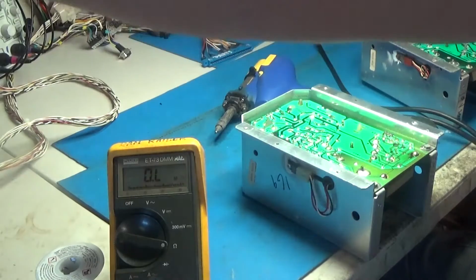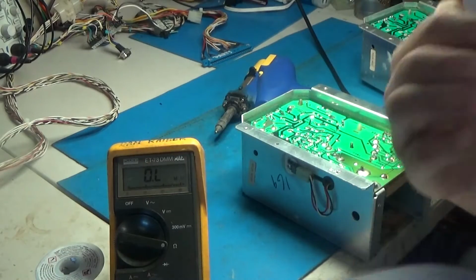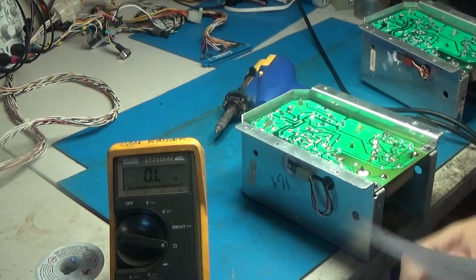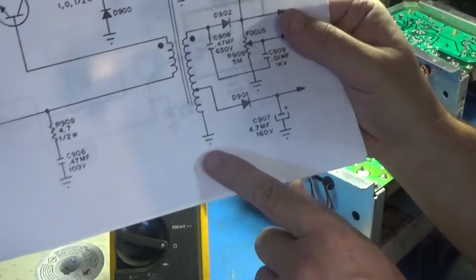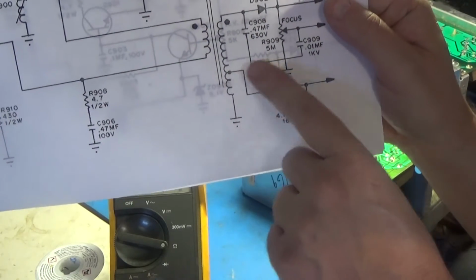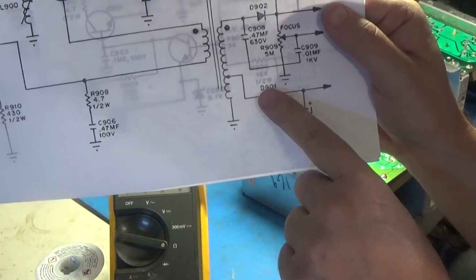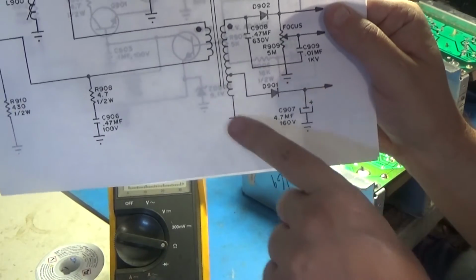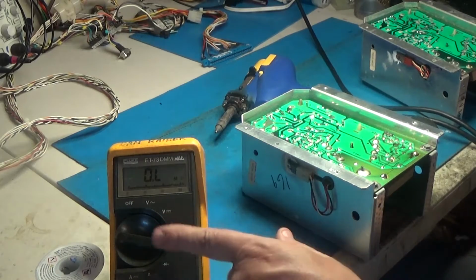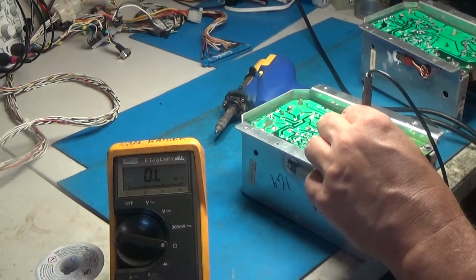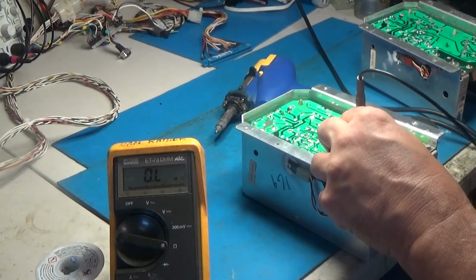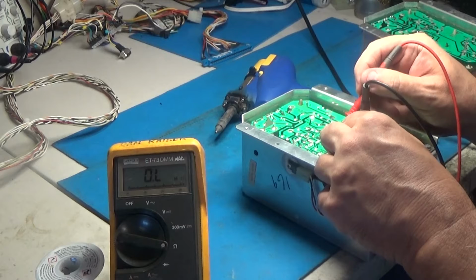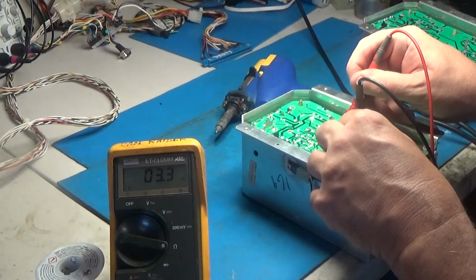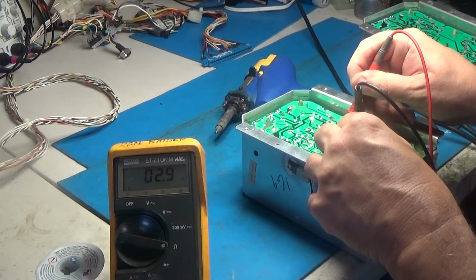Remember the schematic, pardon me, says that there is a winding right here from ground to the point that goes to the anode of D901. There's a winding there. So if I take ohms mode and go to the ground and then go to the lead of the transformer that goes to the anode of D901, you see we get 3 ohms, which is an extremely low resistance. That's that winding.